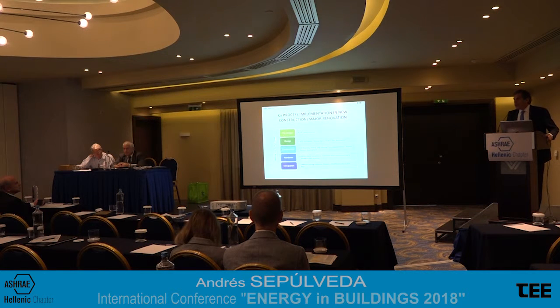The primary intention of commissioning is to fulfill the owner project requirement throughout all project phases. At the pre-design phase, the commissioning process should address and understand the owner project requirements — the wishes of the owner. During the design phase, the purpose of commissioning is to check if the basis of design is compatible with the owner project requirements, and to deliver a commissioning plan that gets updated throughout the project duration.